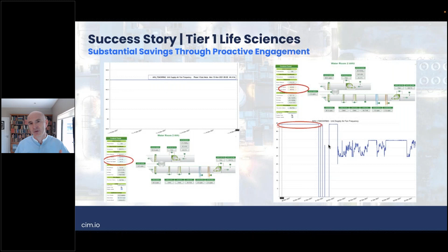This one is, again, just showing the energy consumption before versus after. What we noticed here was that there was an air handling unit that had a hot water loop that used to have to run 24/7 because it wasn't properly treated from a chemical corrosion perspective, so they had to keep the water moving. We knew that to be the case, and the BMS was actually flagging that as a low-level alarm as well. But what was also happening was that it was bringing on the air side, so the fans were coming on even though there was no heating requirement, no heat transfer required at the time. So this was around operational issues where plant and equipment is running unnecessarily.